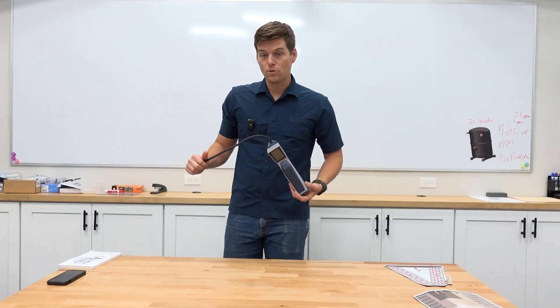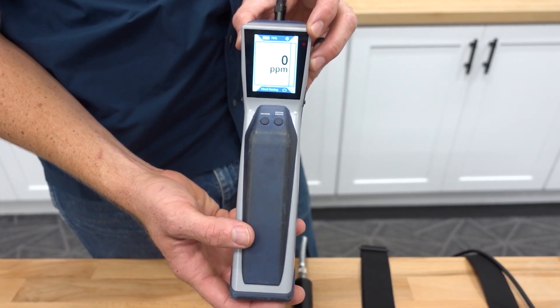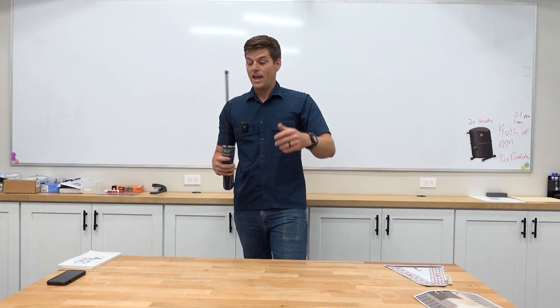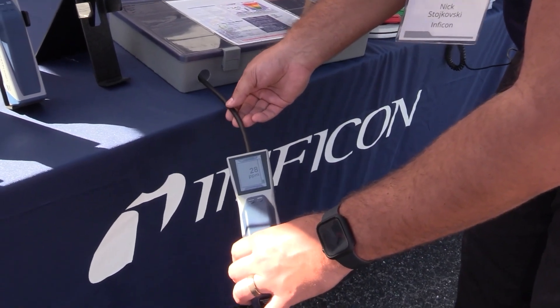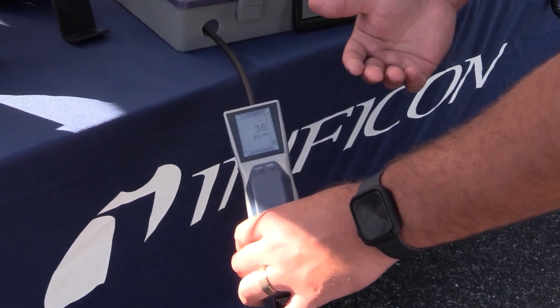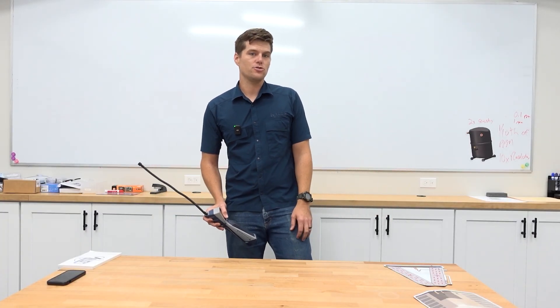Our friends over at True Tech Tools sent us over a really cool leak detector, which we're going to get to, but everybody knows what this is — this is the INFICON Stratus. The Stratus has a mode called Cloud Function that allows us to walk into a building and read the parts per million of refrigerant in that space, and actually find where that leak is based on concentration rising or falling. This comes in handy with large buildings, large package units, rooftop units, crawl spaces, attics, or even refrigerant rack houses for commercial refrigeration.